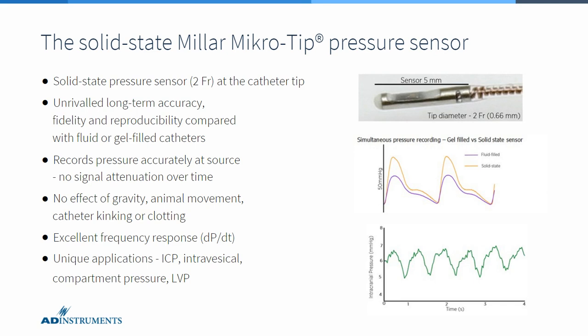The reason for this is that pressure is recorded directly at the source where this sensor is implanted, at the end of the catheter. If you're recording arterial blood pressure, for instance, this part of the catheter is implanted in the artery, and you're recording the signal directly via this small window, which is how the pressure waveform is detected.